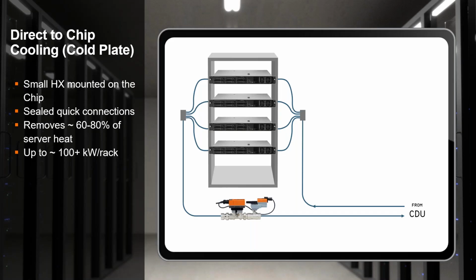And if you need to change the flow rate because you put in different servers and suddenly needed 28 gallons a minute, as long as there's capacity left in that valve, you simply reprogram it or give it a different control command, and now it's going to control to 28 gallons a minute. The Belimo EPIV is really good at being flexible, and it makes you a little bit future-proof if you size it properly on the way in.